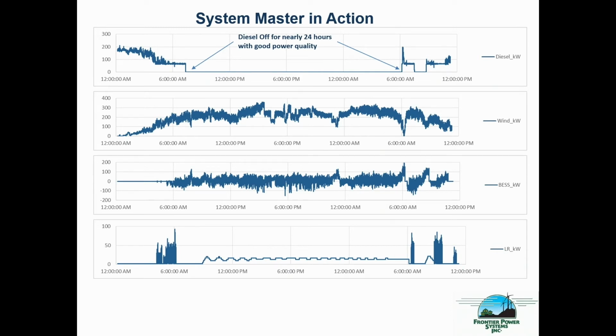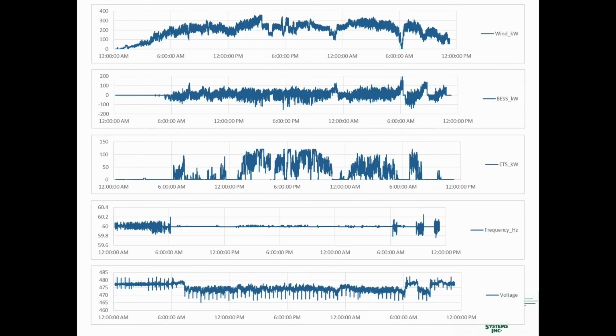This would have been when the diesels were at minimum load, the BESS wasn't ready to come on, the wind had picked up, and the load regulator had to absorb that power. These are some more graphs of the same system.